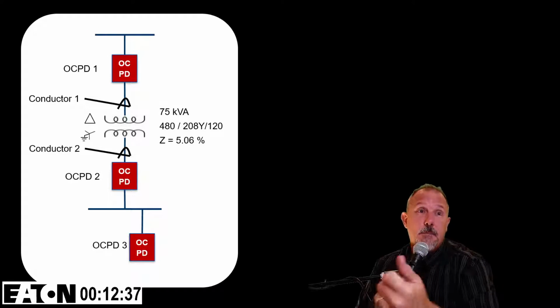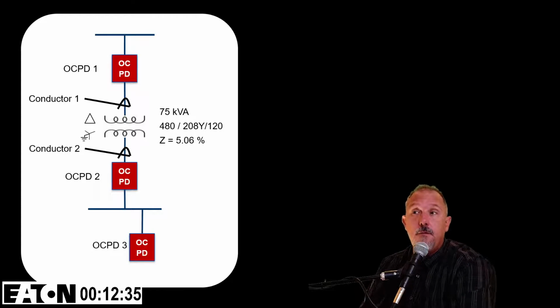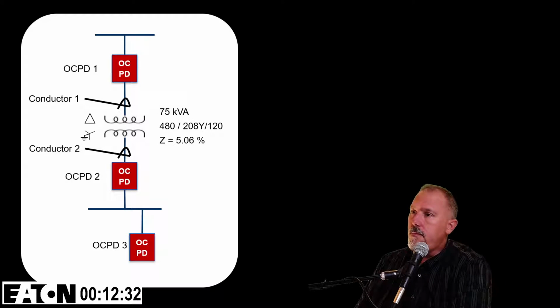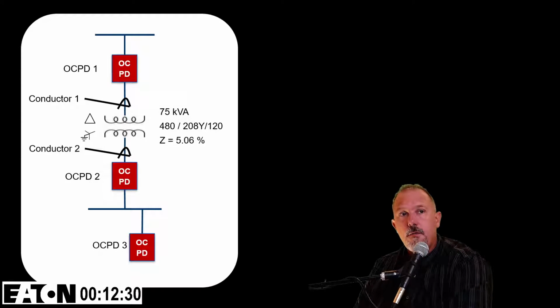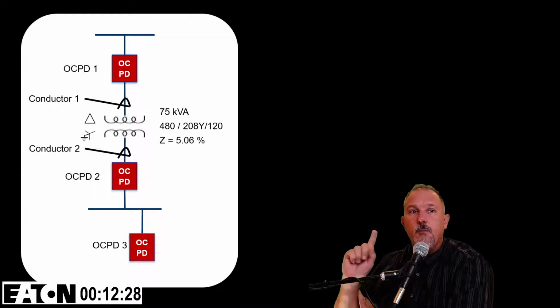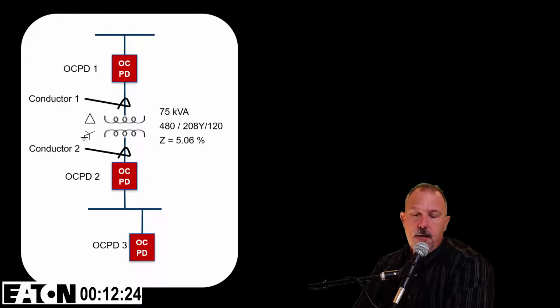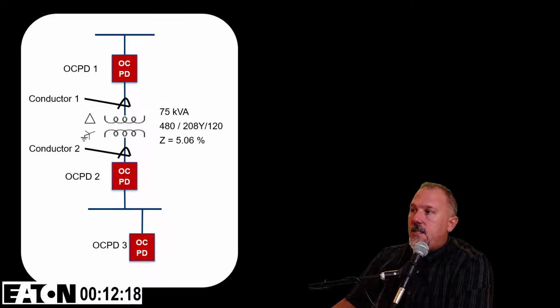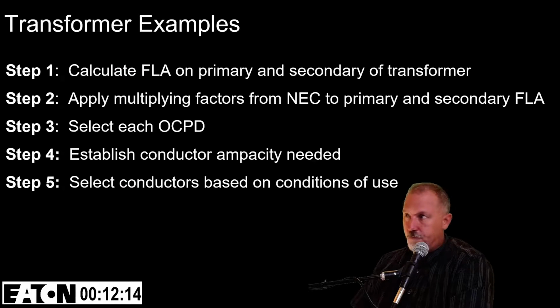Suffice it to say that that primary device has to be able to interrupt the available fault current at its line terminals. So I'm going to work through picking overcurrent protective device number 1 and 2, conductors 1 and 2. I'm not going to be worrying about device number 3 down there in the bottom, because that's just not part of my job at this point, not part of this program.